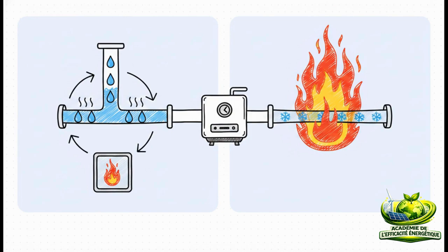When your steam actually does its job and transfers its heat out in your facility, it turns back into liquid condensate. Now, this condensate is hot, usually sitting somewhere between 130 and 225 degrees Fahrenheit. The more of this hot water you can pipe back into the boiler, the less cold makeup water you have to pump in. And since that cold makeup water is usually chilling at around 50 to 60 degrees, bringing it all the way up to boiling takes a huge amount of energy. So reusing your condensate drastically cuts down your fuel burn, slashes the chemicals you need for water treatment, and seriously lowers your sewage disposal costs.